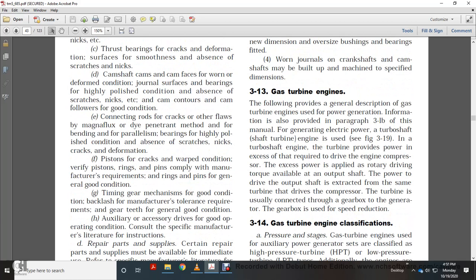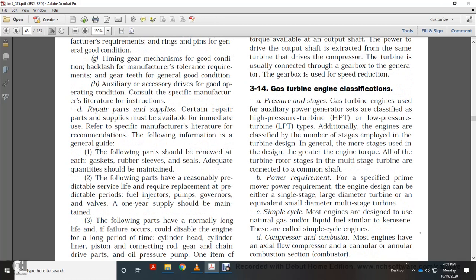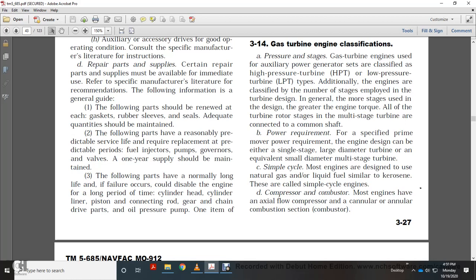Section 3.13 — Gas Turbine Engines. A turbo-shaft gas turbine provides power in excess of that required to drive the engine compressor; the excess power is applied as rotary driving torque to the output shaft to drive a load. Section 3.14 — Gas Turbine Engine Classification. Gas turbine engines for auxiliary power generation are classified as high pressure turbine and low pressure turbine. Additionally, engines are classified by the number of stages employed in the turbine design; generally, more stages produce greater engine torque. Power requirements can be met by either a single-stage large diameter turbine or an equivalent multi-stage small diameter turbine.